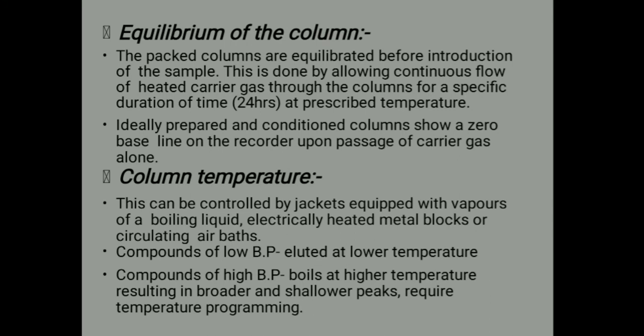Equilibrium of columns: the packed columns are equilibrated before introduction of samples. This is done by allowing a continuous flow of heated carrier gas through the column for a specific duration of time, around 24 hours. An ideal prepared and conditioned column shows a zero baseline on the recorder upon passing of carrier gas alone. Talking about column temperature: this can be controlled by a jacket equipped with vapors of boiling liquid, electrically heated metal blocks, or circulating air baths. Compounds of low boiling point are eluted at low temperature, while compounds of high boiling point require higher temperature, resulting in broader and shallower peaks, requiring temperature programming.